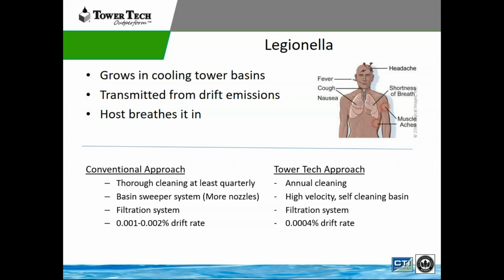The conventional approach is thorough cleaning, at least quarterly, basin sweeper systems, a filtration system, and then a low drift rate for that conventional tower system. Tower Tech's approach is annual cleaning. We're using a high velocity basin on our water collection, where the water is moving 5 to 7 seconds, which makes it very tough for Legionella to grow in a tower that has no exposed sunlight, so no algae, and where the water is always moving. Then obviously a filtration system, but our drift rate is far less.